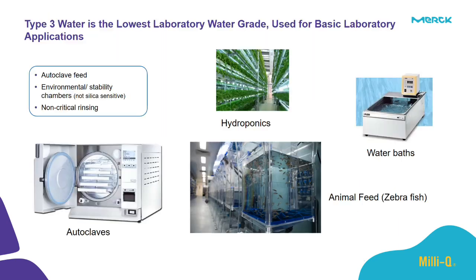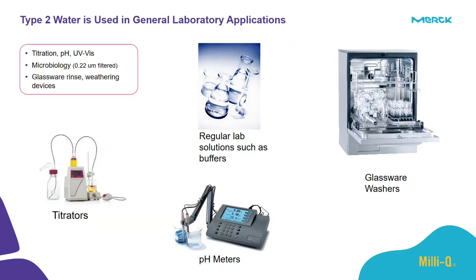Let's have a general overview of the applications we use type 3 for. It can be used for autoclave feeds, environmental stability chambers, and non-critical rinsing that is not silica sensitive. Type 2 water is used for general laboratory applications such as titration, pH, UV, microbiology with a 0.2 micron filter, glassware rinsing or final rinsing, and washing devices. Regular lab solutions such as buffers should be made with type 2 water, as they consume large quantities of water. Also, the final glassware washing should use type 2 water. Titrators and pH meters can also work with type 2 water.